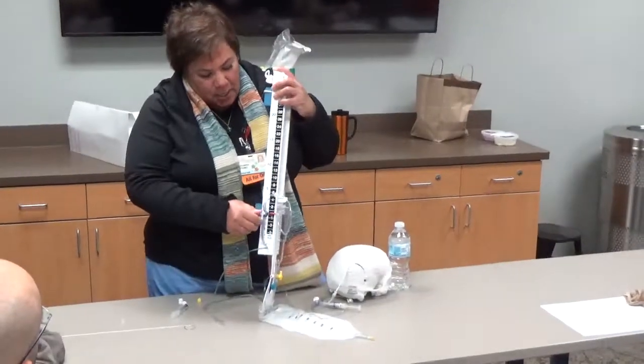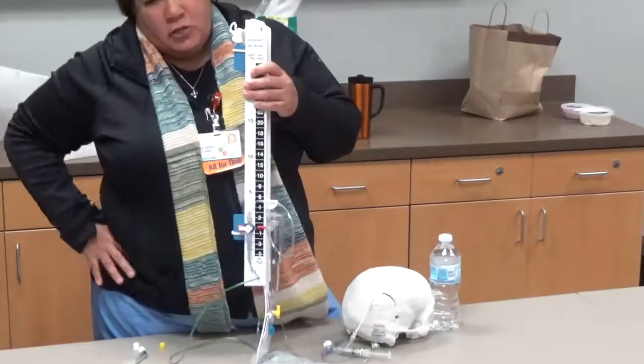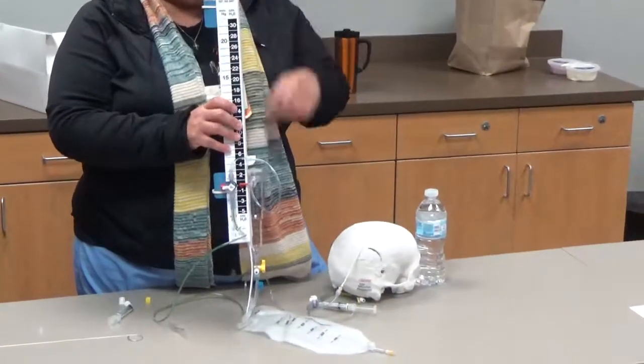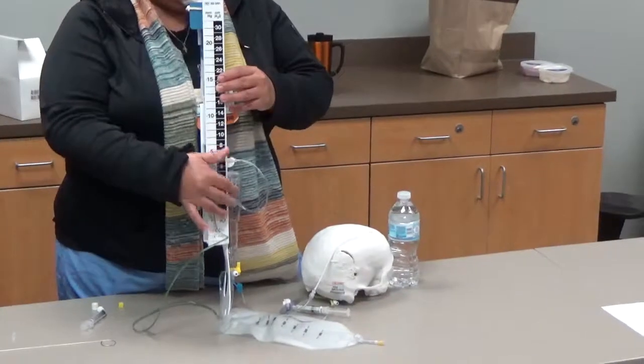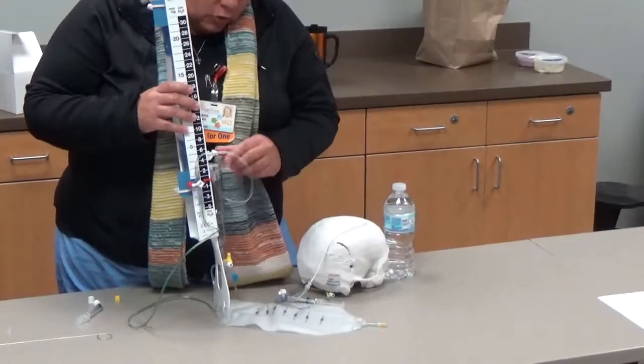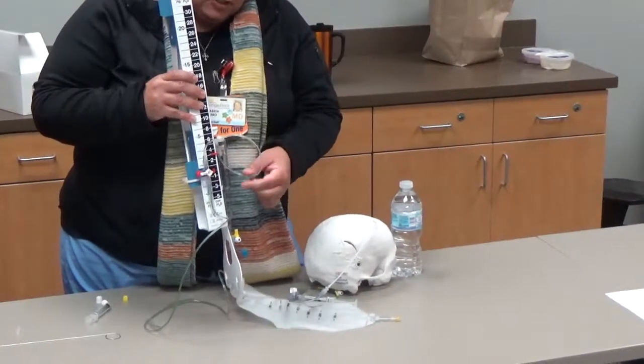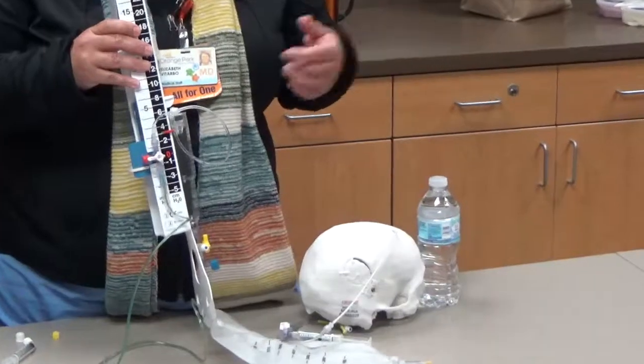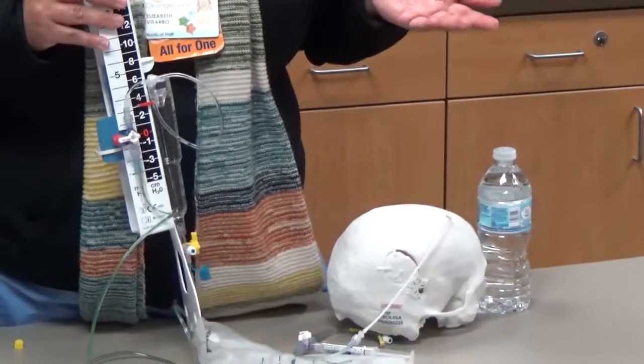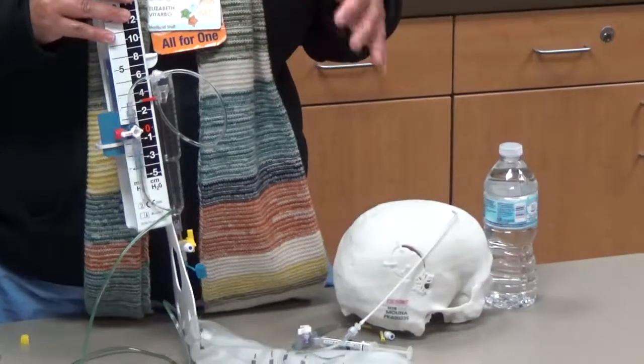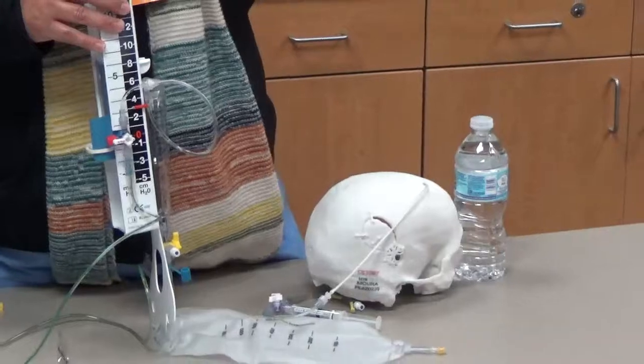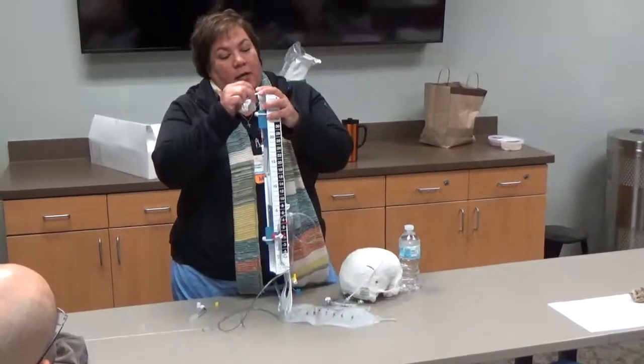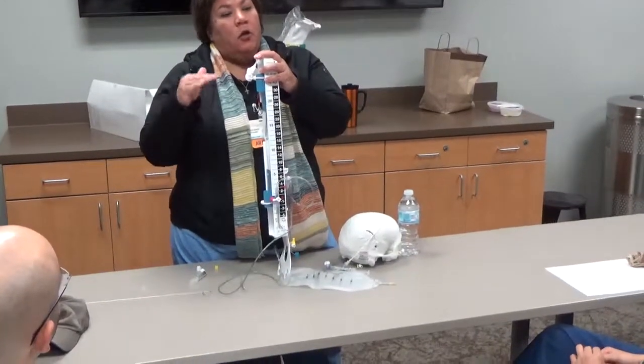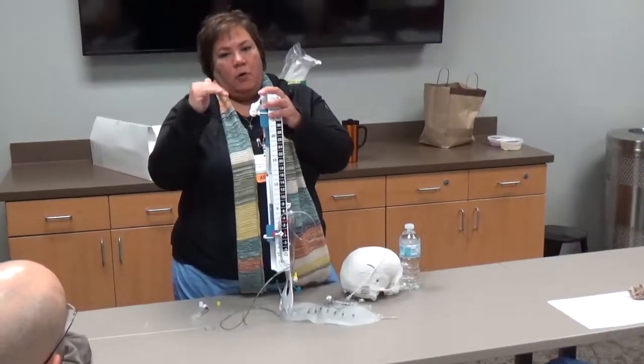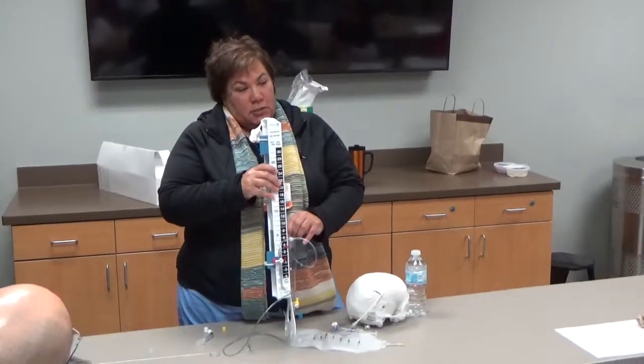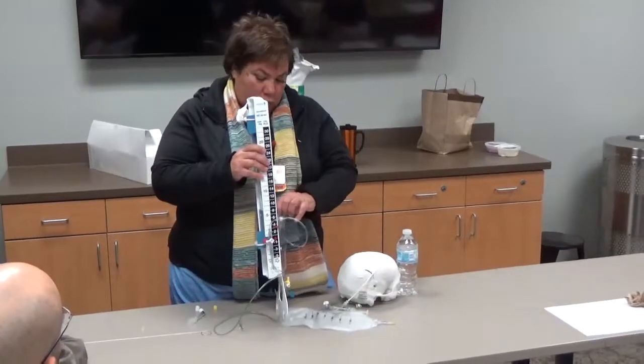So the way I do my manual ICP is I'm off to transducer. I now have the fluid column coming from the patient to my chamber, right? You can see that somewhere in the tubing you'll always find a meniscus. You'll more than likely have an air bubble you could follow also. But you'll probably find a meniscus, and if it's a live patient that's not brain dead, they will have pulsations in a waveform, right? So you will see those pulsations in the fluid column. You should see those pulsations unless they have crazy high ICP or they're brain dead, or your catheter is totally screwed.